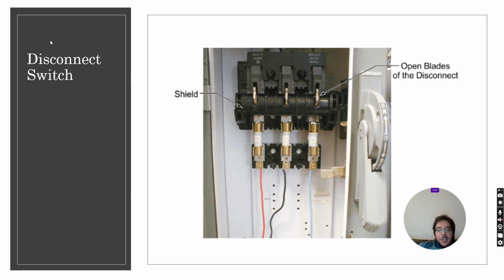Now, in a disconnect switch, this one's fused, which means it's got fuses. If too much power goes through, instead of tripping or opening the switch, the fuse melts, and there's no more power flowing through the fuse, so that physically cuts it off. The only way to get the power back is to put a new fuse in. But at the same time, we can manually turn the switch off by turning it into the off position. So it's got two different safety mechanisms here.